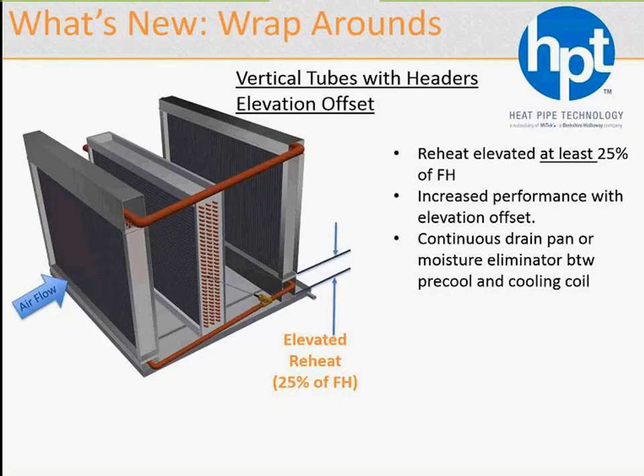arrangement, a continuous drain pan is needed to capture condensate as it'll tend to blow off from the pre-cool to the next coil downstream.